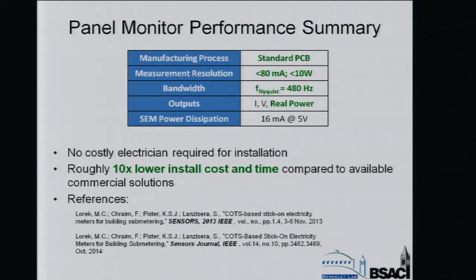So in conclusion, about the panel monitor: this uses a standard PCB manufacturing process. We can measure real power down to below 10 watts. This slide is a bit out of date - actually the bandwidth of our analog front end is 960 hertz. We can measure current, voltage, real power, and the power dissipation of the sensor itself is about 16 milliamps from 5 volts. So the hardware is low cost, and it doesn't require an electrician to install. This represents roughly 10x lower install cost and time compared to commercially available solutions which use current transformers.